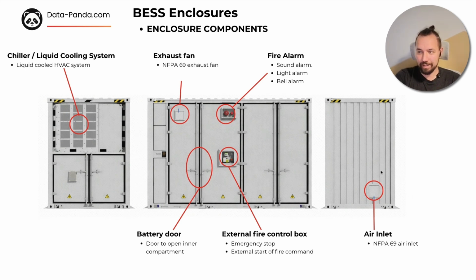Then we have the air inlet. Again, NFPA 69 compliant. So it supports controlled airflow. It allows inflow of air. So in the case of emergency ventilation events, it ensures that we have exhaust of air and at the same time we have air coming inside, so we can quickly remove the gases and replace them with air from the outside.